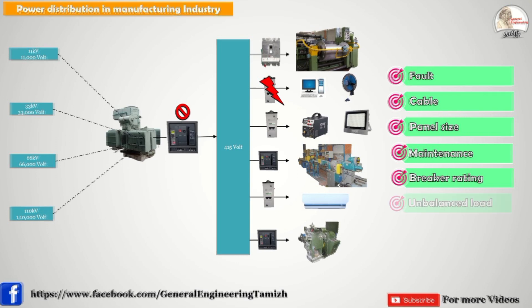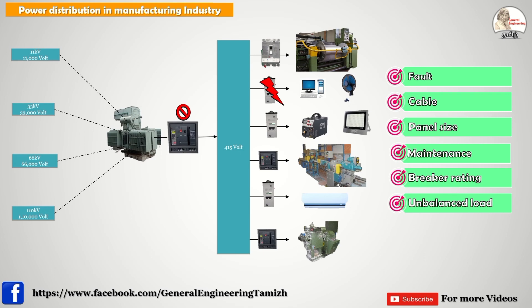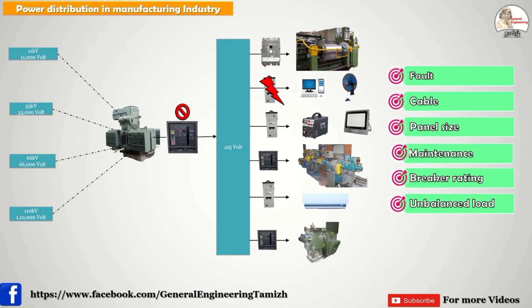The next scenario is unbalanced load. We have three phases — R, Y, B — and we must connect loads equally across all three phases. If R phase has 10 lights, Y phase should also have 10 lights. If Y phase has 50 lights the breaker will trip due to unbalanced load. In this single panel setup, you cannot choose phases properly — wherever space is available you connect the load — so balanced distribution is not possible.